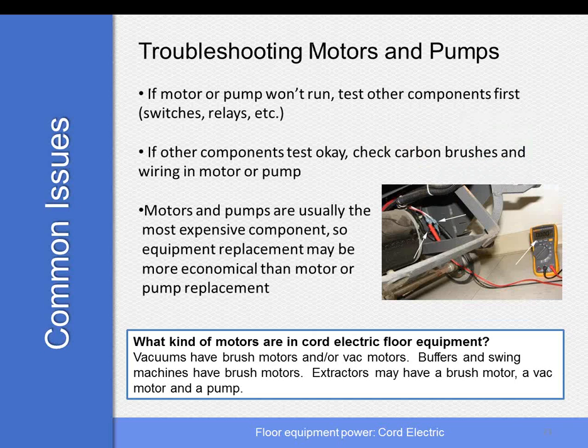When you're trying to troubleshoot a motor or a pump, if the motor or pump doesn't run, it's best to check the other components first, and that's why in the beginning we're looking at the switches, and then the relays, and then rectifiers and all that. If all those individual pieces are fine, then we need to look at the motor. If it's a DC motor, let's look at the carbon brushes. Like I said, they're really easy to change out and also fairly inexpensive.